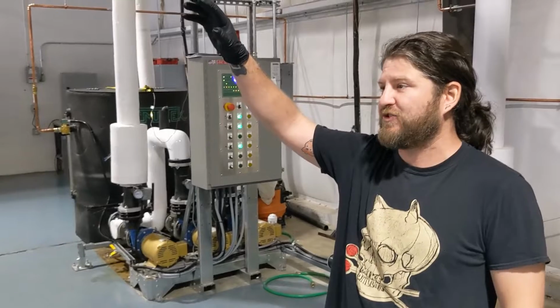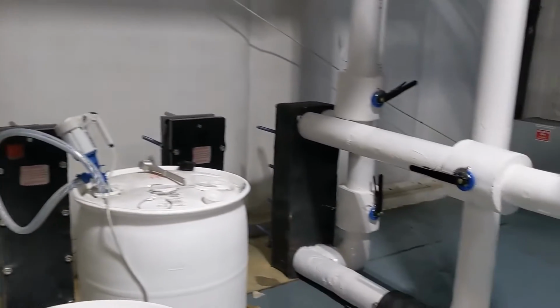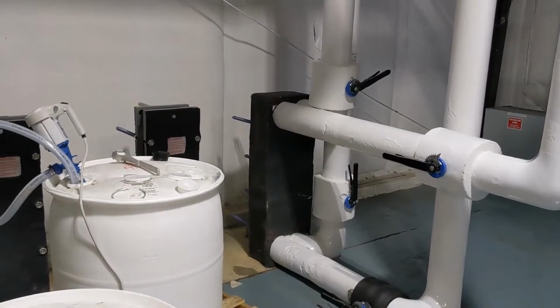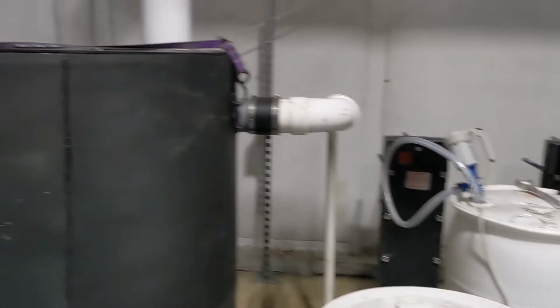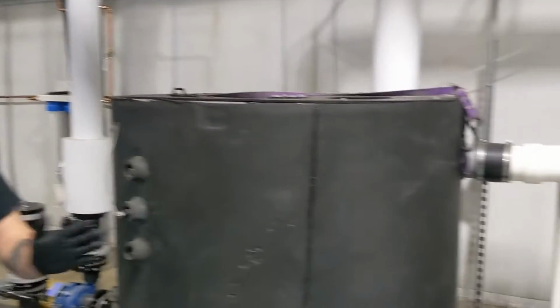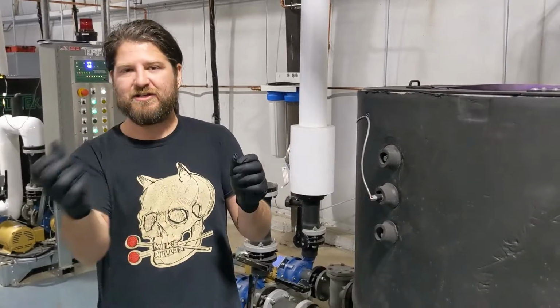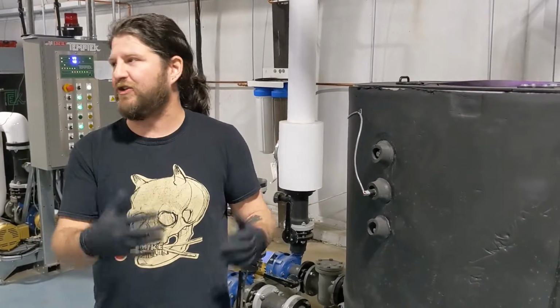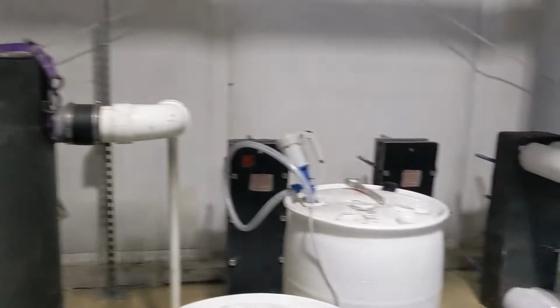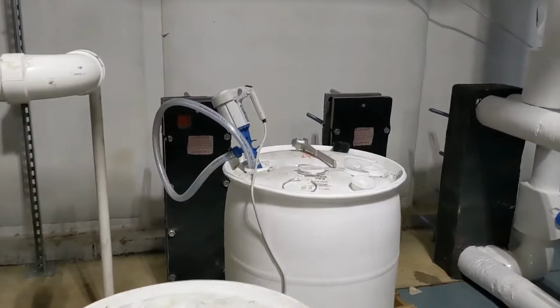Then on the other side here is our process water. That's the water that actually goes to the presses, that's cold. But over here on that heat exchanger, because we don't want glycol making its way into the presses or the boiler or anything like that, because we'll just ruin it all, we use that heat exchanger, which is split down the middle, and it's a heat transfer without liquids actually touching. So this side goes out to the chiller, and this side runs to the process loop over here.